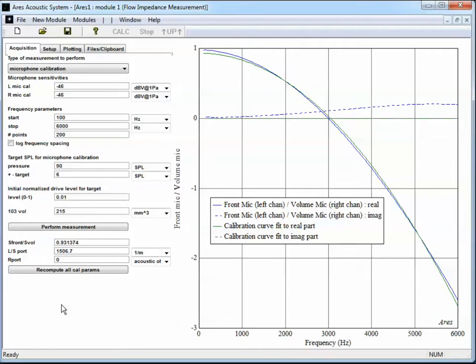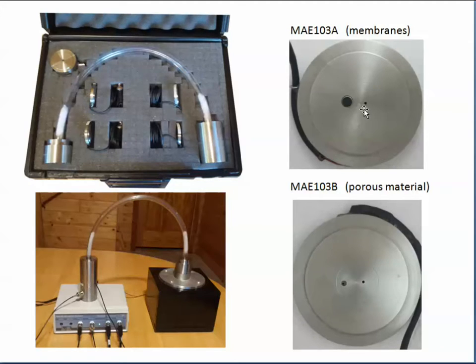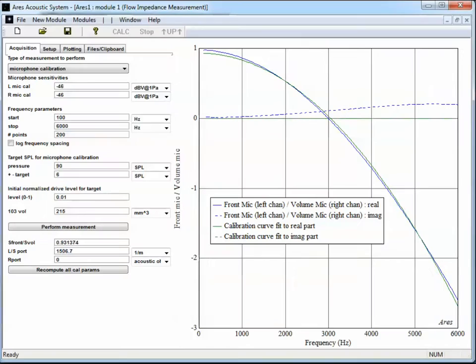The manual describes the fact that you can drill the sample holder measurement port open to be a larger diameter if you so choose. If you do that, you do change how these parameters will appear. So you will get a change in these if you do change the measurement port size. But we're getting a reasonably good fit with the measured data to the parameters that we have here.